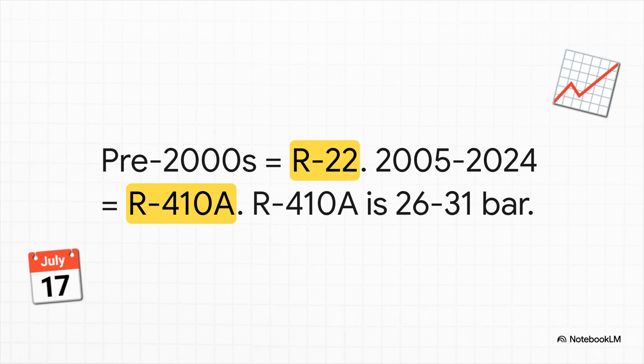Well, age is your very first clue. Pre-mid-2000s, it's likely R22. Installed between roughly 2005 and 2024, that usually points to R410A. And anything 2025 or newer is going to be an A2L, like R32 or R454B. But here's the thing. The pressure gap between these is huge and incredibly dangerous. R410A operates at 26 to 31 bar on the high side. That is 50 to 70% higher pressure than R22. This is exactly why mixing them will literally crack fittings and violently burst an R22 compressor.